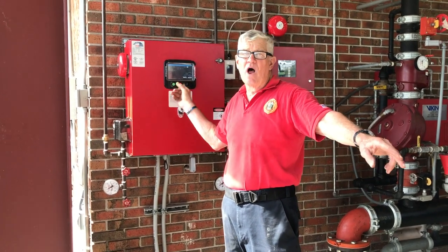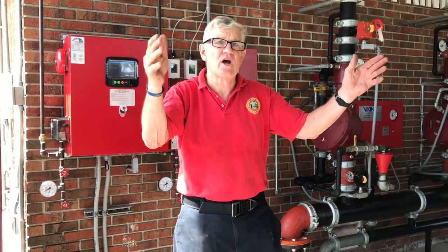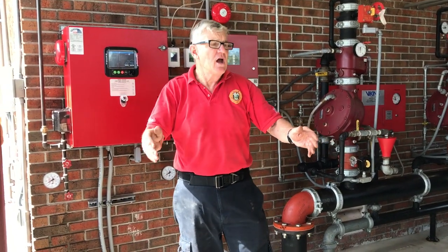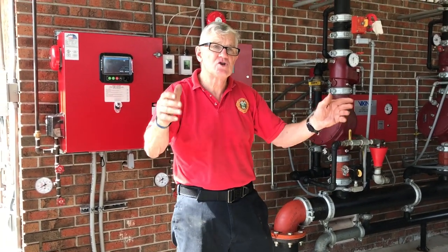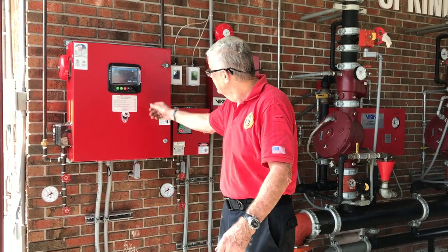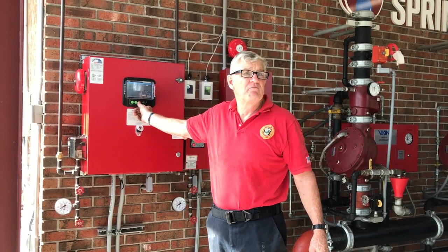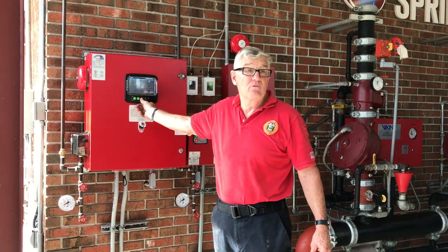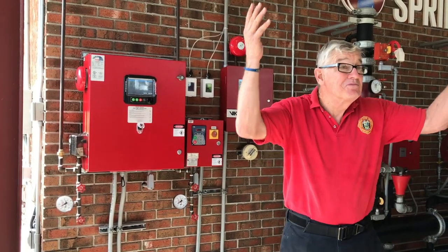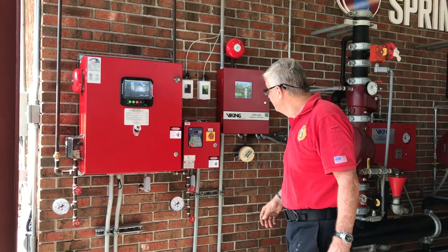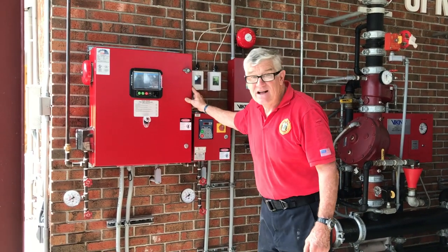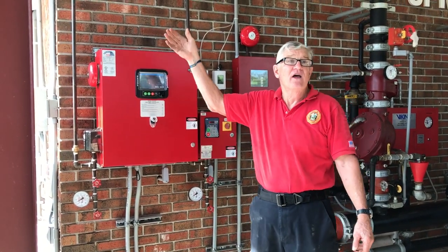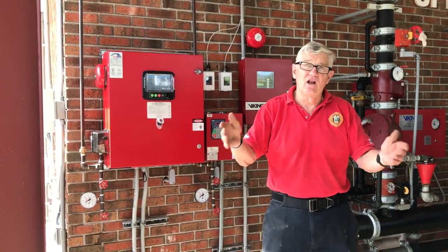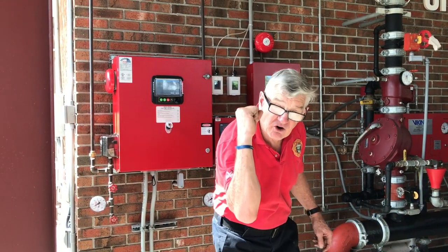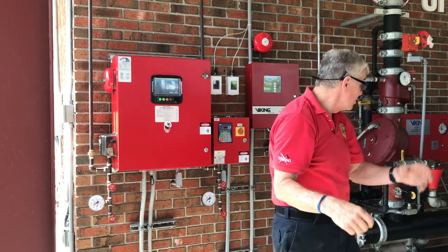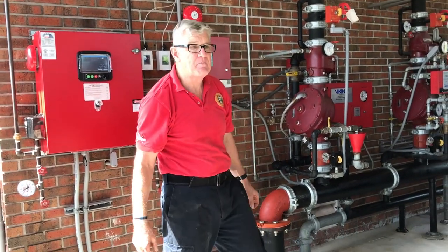A diesel pump will run for a half an hour with no demand and shut itself down. An electric pump will run for 10 minutes, then shut down. If there's no demand, all you have to do is press the off button. If there is a demand, when you take your finger off the off button, the pump's going to start right back up. If that's the case, then you're going to have to shut it off at the main disconnect if it's an electric pump. Remember, transfer switch first, main control, and of course the jockey pump control.